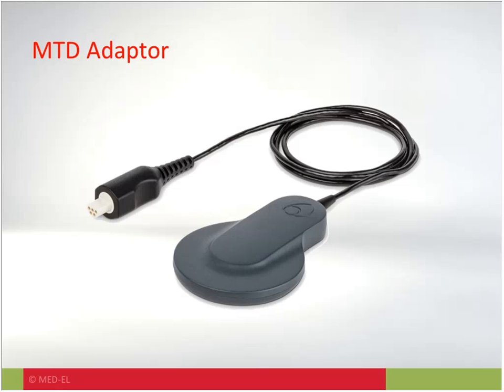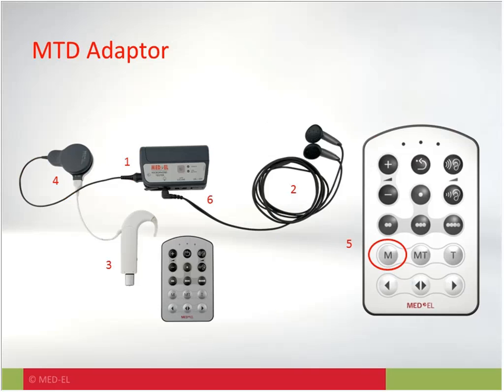So if you're familiar with our other way of checking listening, the speech processor test device, this is totally different. Basically, the speech processor test device, that little gray paddle that you see that has the red light that flashes, just ensures that sound is reaching the coil and that there aren't any hiccups along the way. But it doesn't tell you about the quality of the sound. This device allows you to listen to the quality of the microphone through both the speech processor and an FM boot. So I'm going to walk you through it so you can get a better idea of what this actually looks like. It looks complicated, but it's actually very simple.